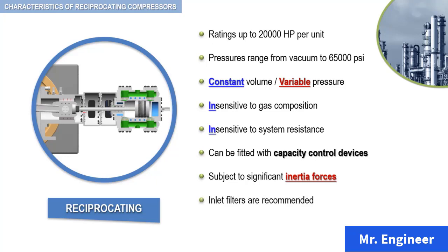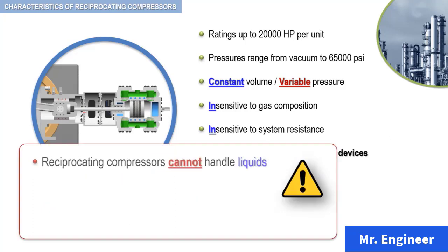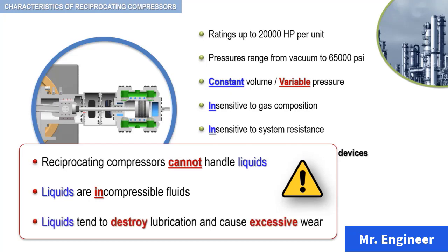An additional point to remember and to keep in mind is that these machines cannot handle liquids that may be entrained in the gas. Why is that? Because first, liquids are incompressible fluids, and second, liquids tend to destroy lubrication and cause excessive wear.